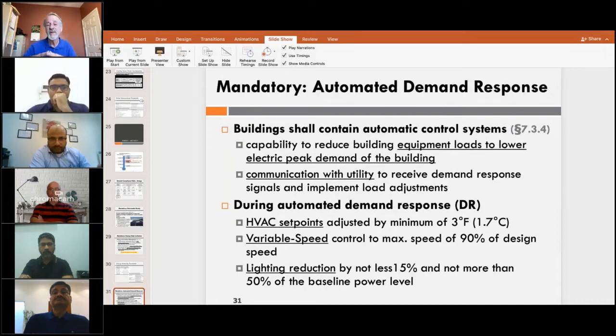at that point. A lot of studies show that if you do this, and maybe if it's done on a gradual stepwise basis, people don't notice. That's really a fairly small change in the overall temperature setting. Other parts to look at: if you have a piece of equipment that has a variable speed drive on it, variable speed control, maybe set the maximum to 90% of the design speed. So a fan is operating, but it's not allowed to operate at 100%, maybe only 90%, and the power consumption for a fan goes basically as the speed of the fan cubed, so 0.9 cubed is more like in the 70% range in terms of the total energy consumption. So that's a significant reduction without really reducing too much of the overall capacity.